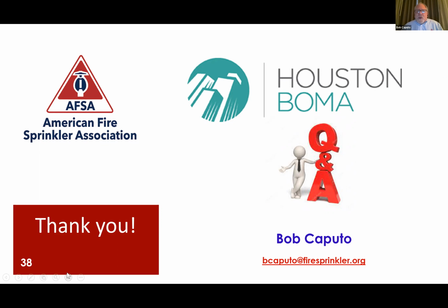All of these things require annual testing and certification, and that should fall to the tenant. It won't fall to the owner. It's like anything else in a triple net lease. The tenant is by default the owner of the fire sprinkler system and bears the burden of inspection, testing, and maintenance criteria and compliance.